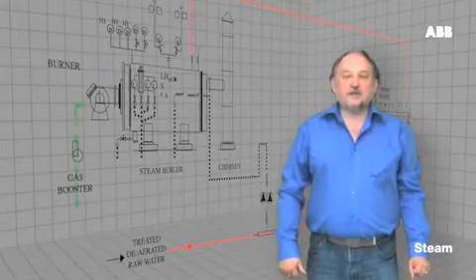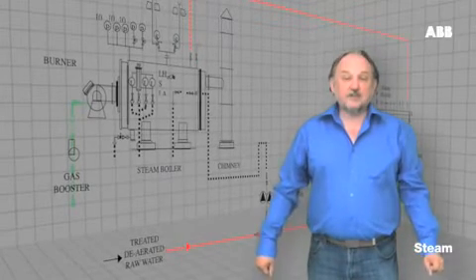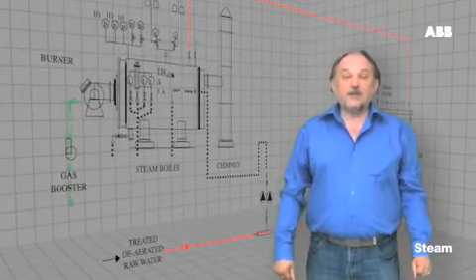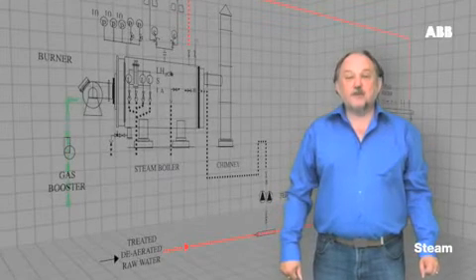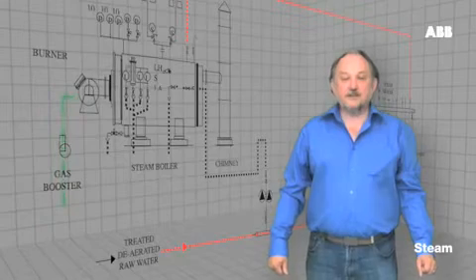To measure dry saturated steam flow through a distribution network or boiler system and work out the amount of steam energy actually lost and used by the network, it's important to compare flow in terms of mass measurement or standardized volumetric measurement to calculate the mass balance.